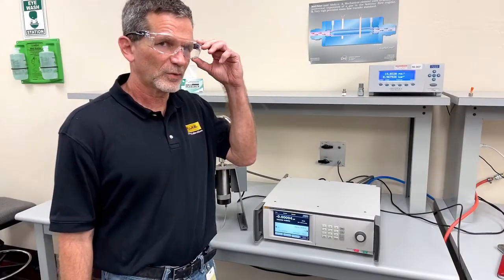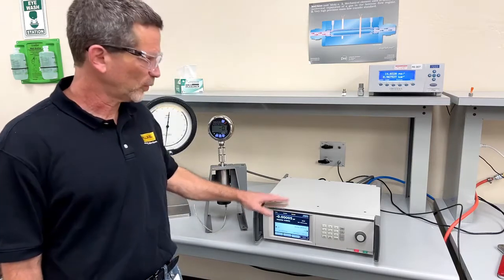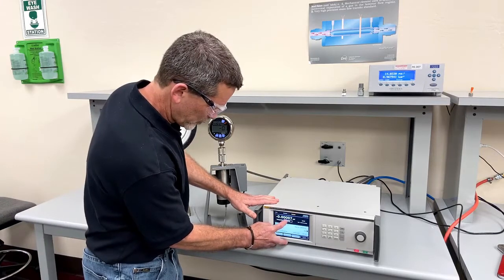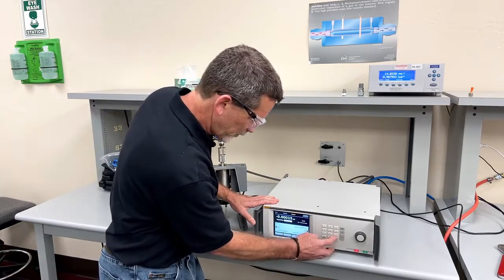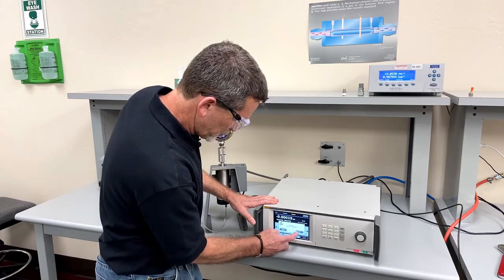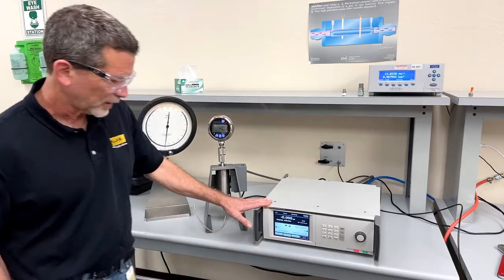In this brief example, we're going to set a 3,000 PSI test point to compare the device under test to the controller, the reference. We simply touch the field corresponding to set point, enter in 3,000 PSI, and tell the pressure controller to control, and it's on its way.